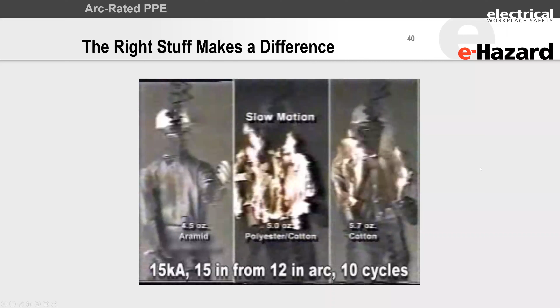Probability of survival goes with this: arc-rated exposure with arc-rated clothing, you're about 95% chance of living. Whereas if you have a shirt that catches on fire, or a shirt and pant that catches on fire, or a coverall that burns off of you, your chances of living go down dramatically, and your quality of life changes quite dramatically after 25% body burn.